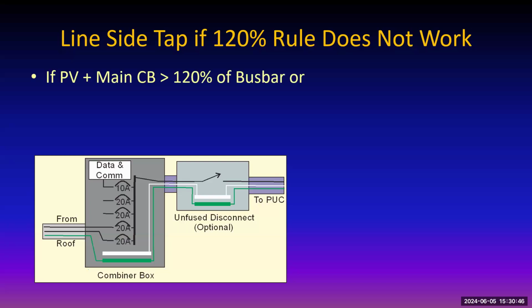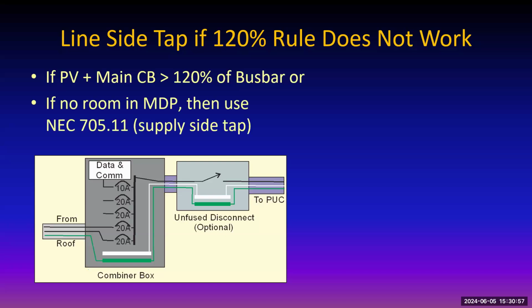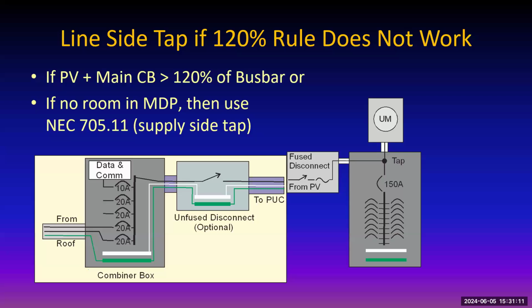Okay. If the 120% rule doesn't work for this, we can do a thing called a line side tap. Start with what came down the last time, but this time, if the PV plus the main circuit breaker is more than 120% of the bus bar rating, or if there's no room in the main distribution panel for that backfed circuit breaker, then you can use a supply side tap, which means we can tap onto the supply wires to the main circuit breaker like this. So you've got the wires from the utility meter going to the main circuit breaker in the distribution panel, and you can connect using a fused disconnect, a 40 amp fused disconnect in this case, less than 10 feet away from where that tap is. And you've met the constraints of 705.11.